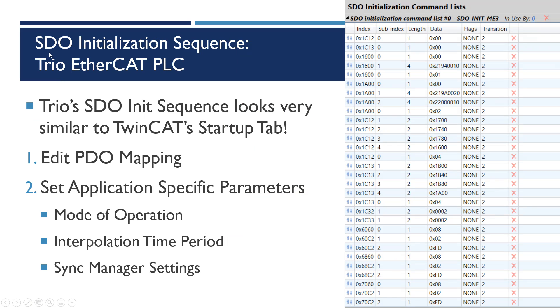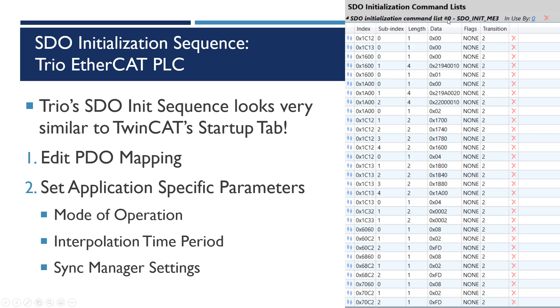To compare, here's what TRIO, another EtherCAT master, has. It looks very similar to TwinCAT's startup tab. You have an SDO initialization command list for each node. So I added a three-axis controller here and this long list of startup. On startup it'll send these SDOs to map the PDOs.